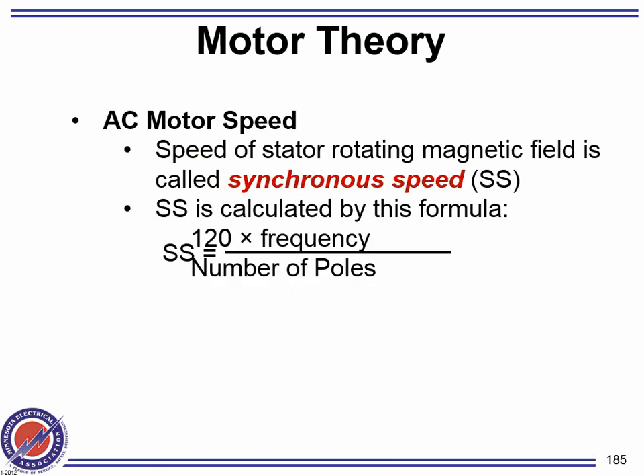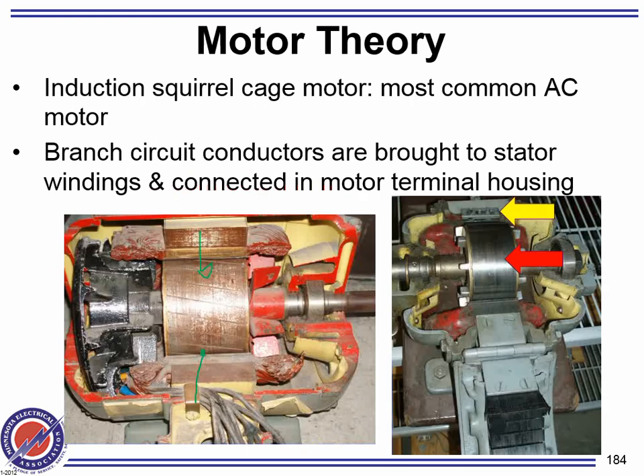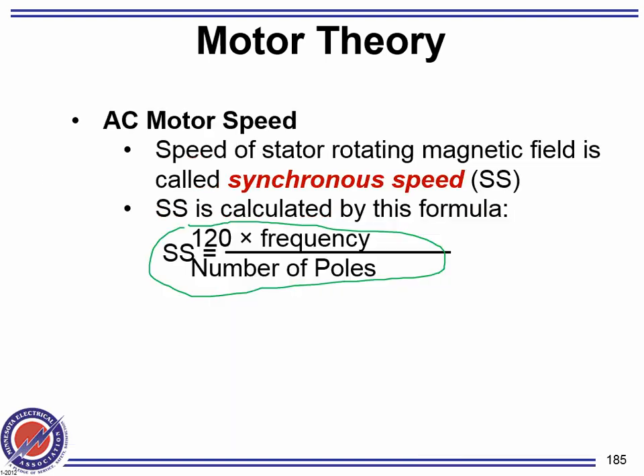Okay, for you guys for the test, test related, you need to know this formula. The synchronous speed of a motor, gentlemen, is the speed of the magnetic field inside the motor. It's 120 times the frequency divided by the number of poles. So they'll ask you to find the number of poles or the frequency. What happens if you want to flip this formula for the number of poles? You swap what by what? Swap synchronous speed with the number of poles. That's it. Swap them.